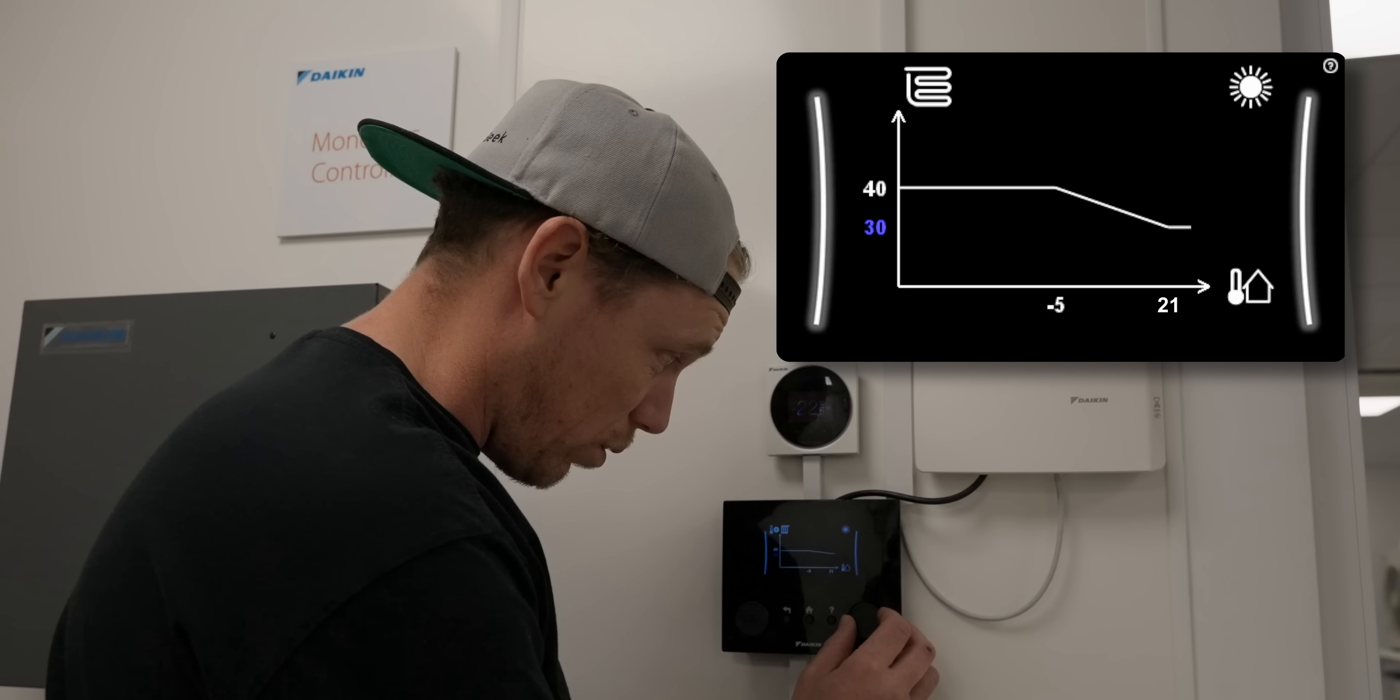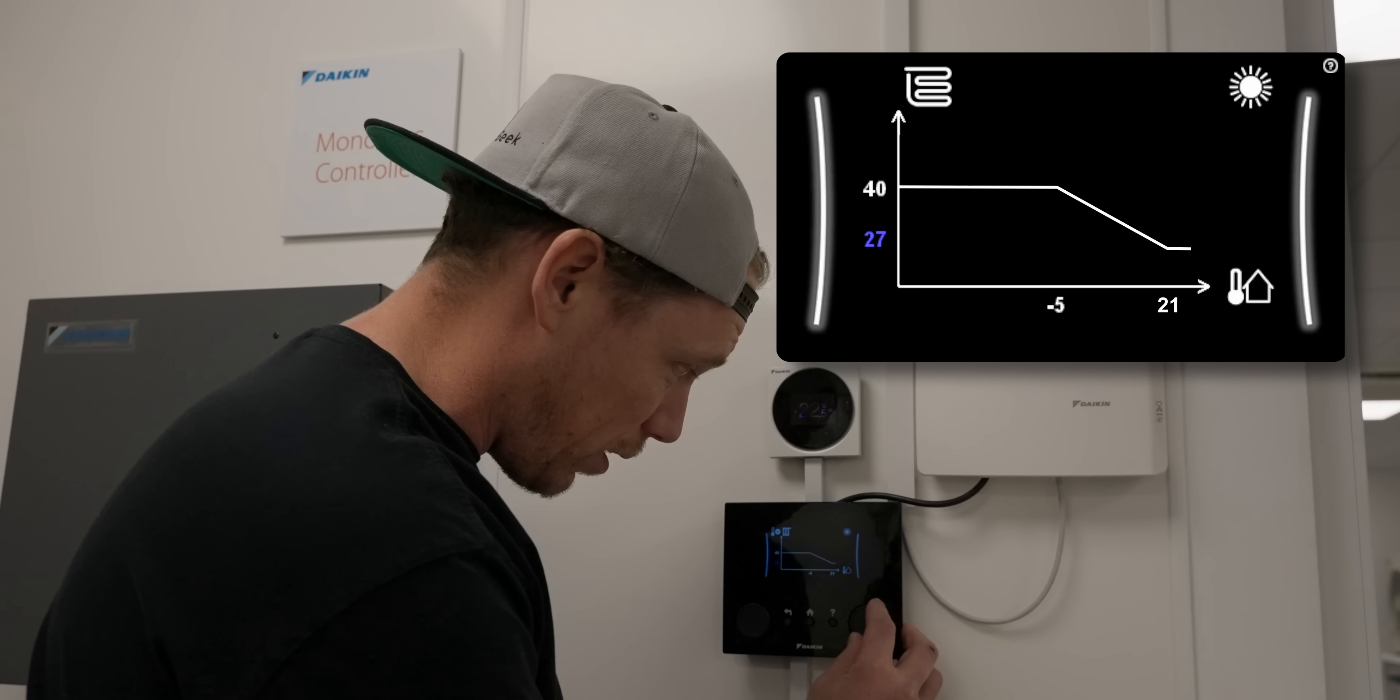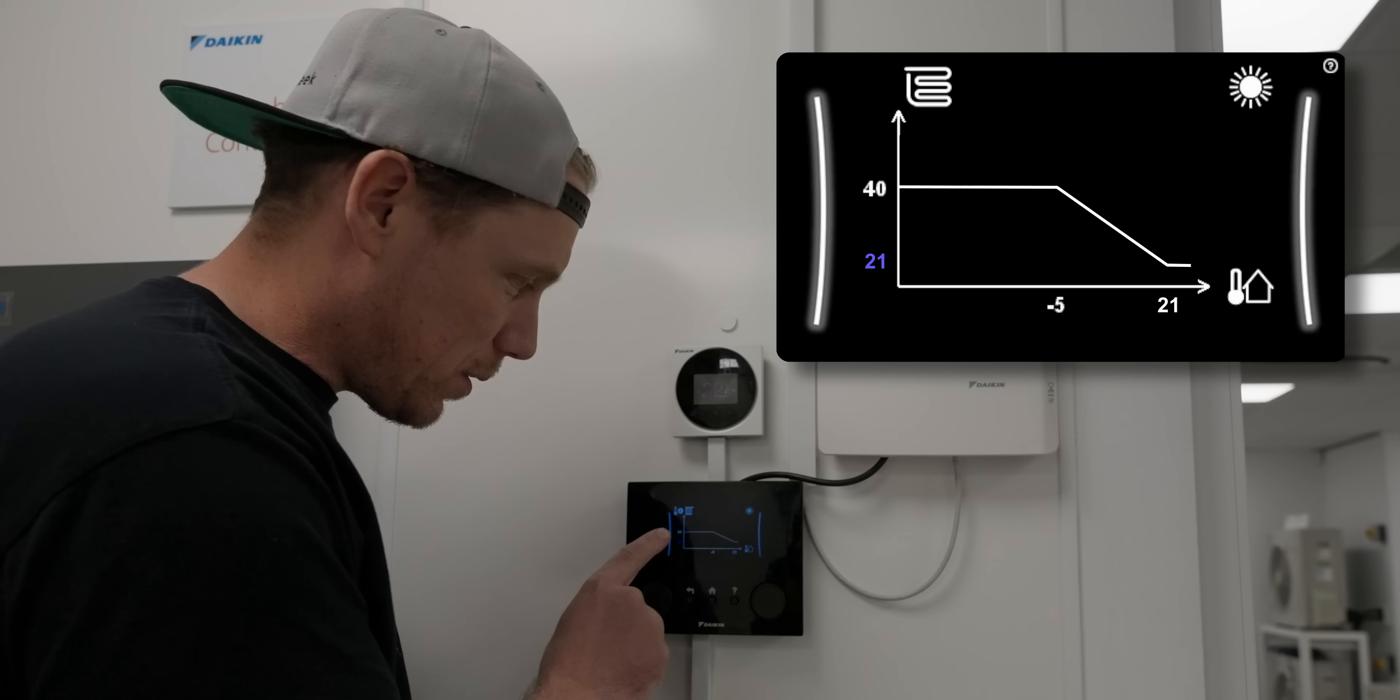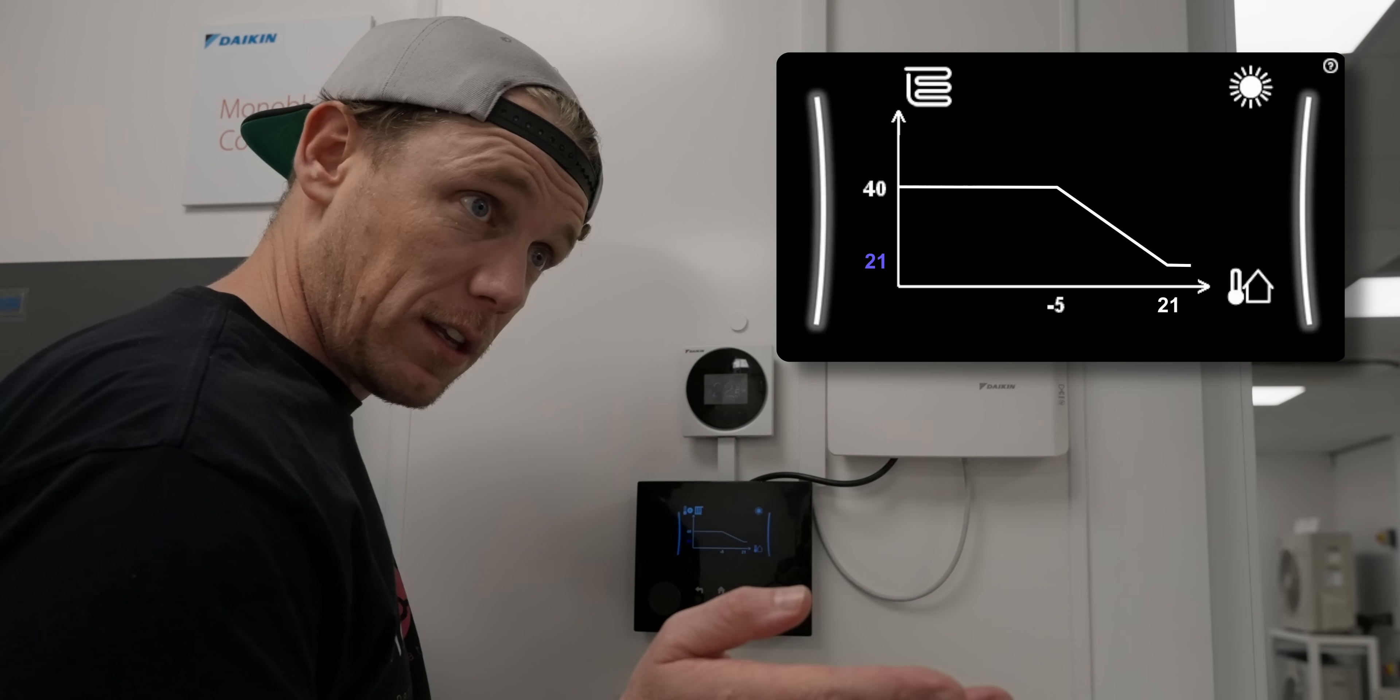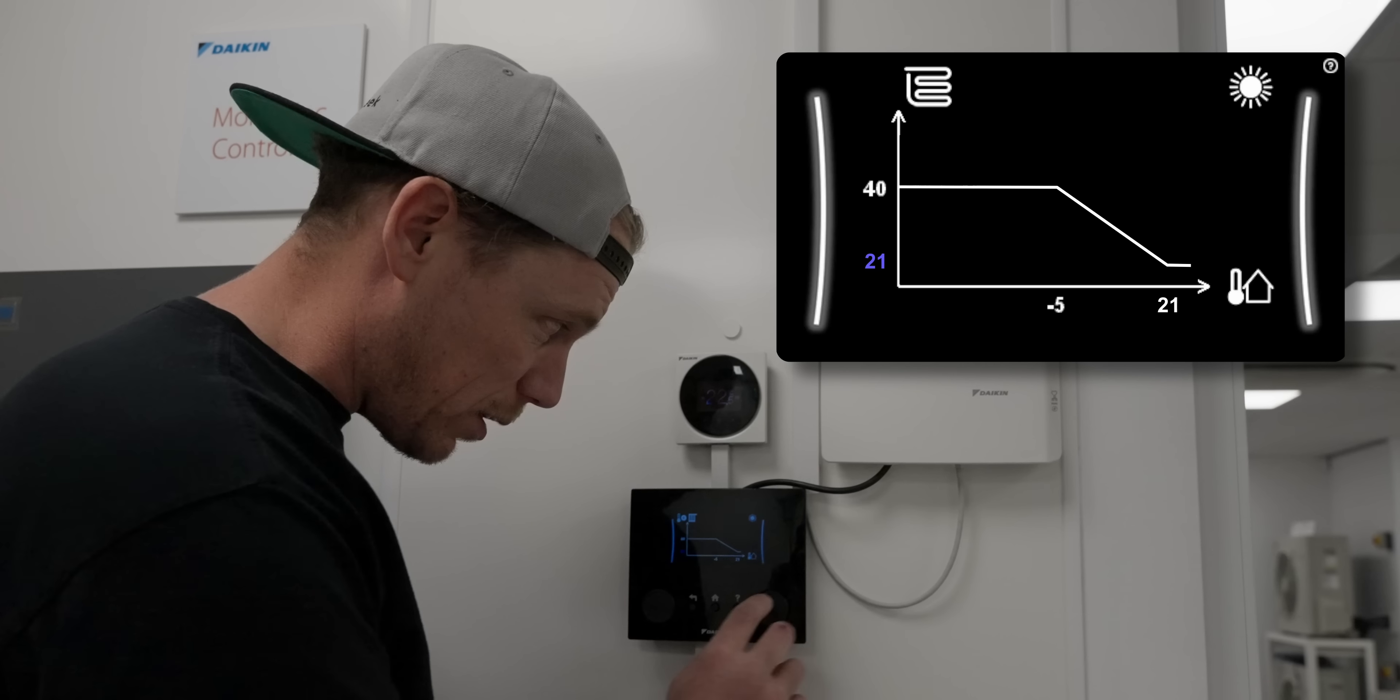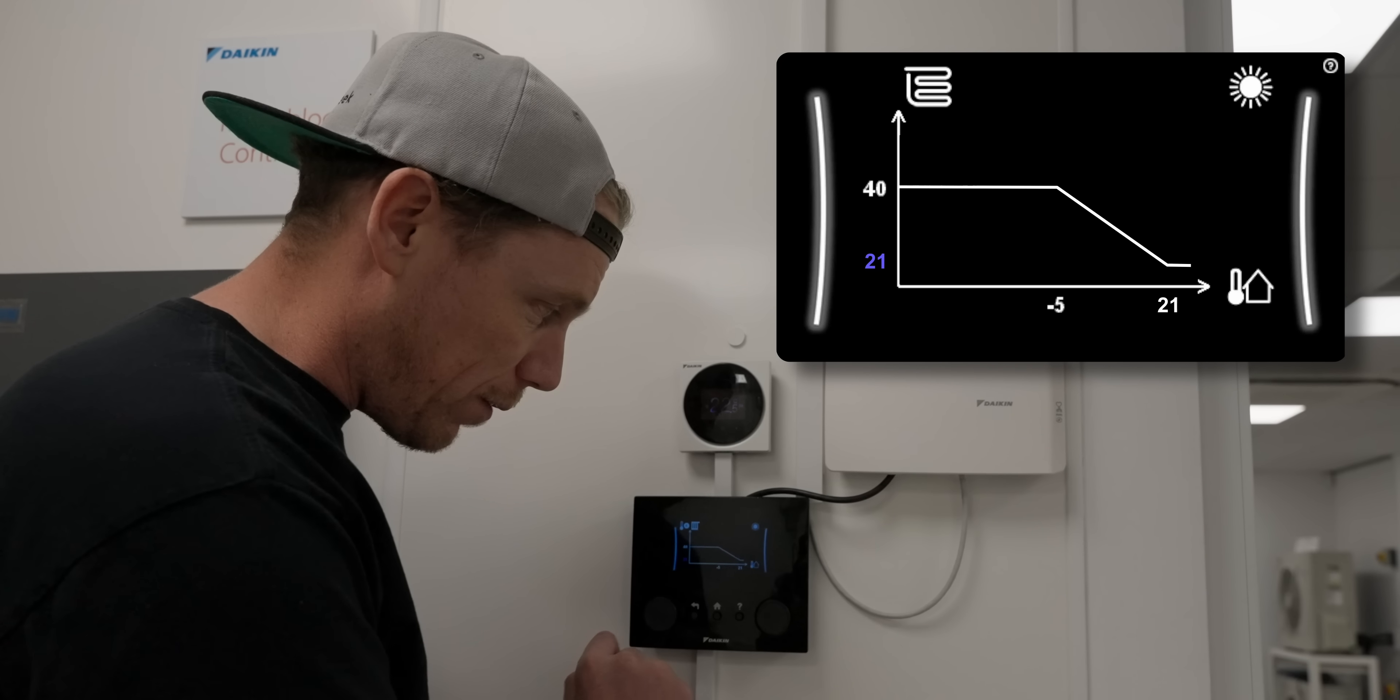And then the minimum temperature I would advise to set to your main room temperature. If you like it 21, I would advise 21. However, the Daikin heat pumps cut out at 25 degree flow temperature anyway to protect the compressor, so it's actually going to stop at 25 degree flow temperature anyway.